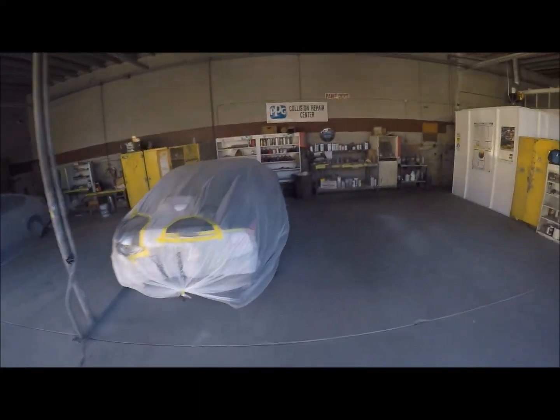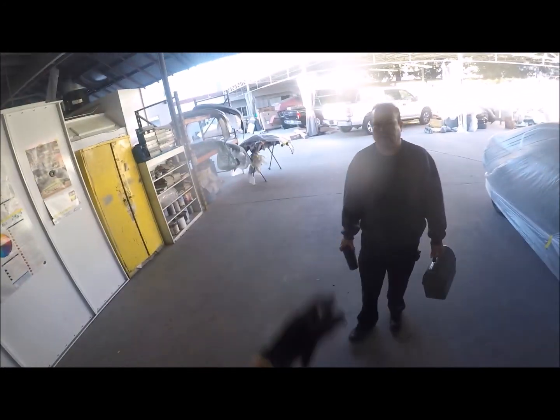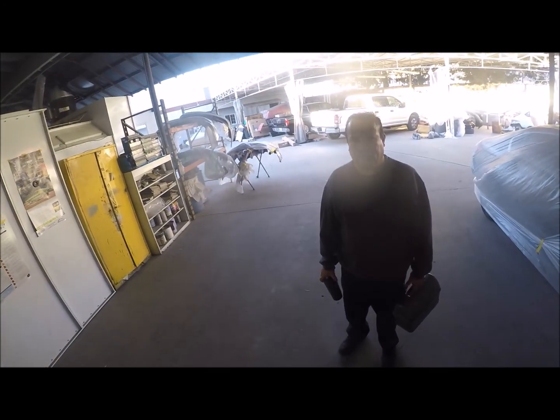Alright, let's come over here and check the rest of our stuff. No, we're not done yet. Oh. I had to change the main. No. From there? It's fried too. Which one? The 220? The three-phase 100 amp feeding this panel. That's the, okay. So what we had was, we had this panel arced up. Yeah. One of the legs, the one that was feeding off of.